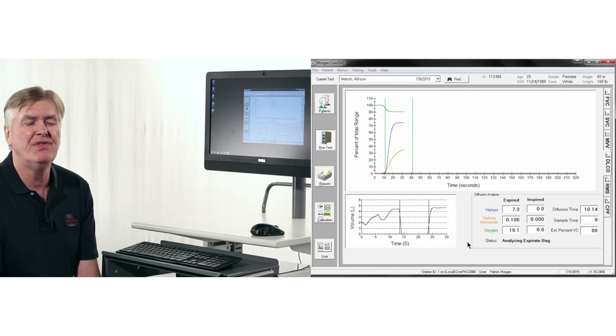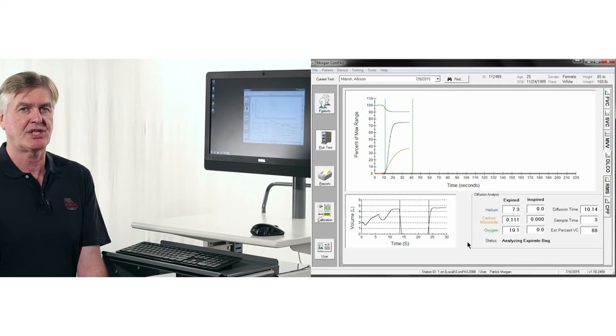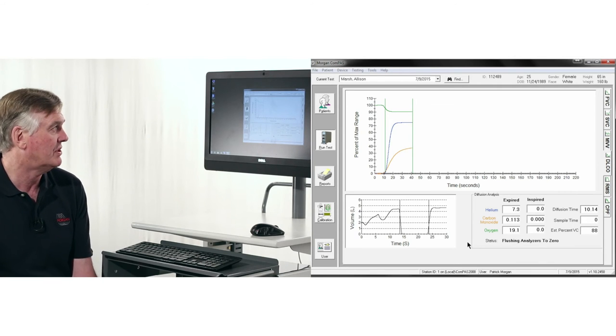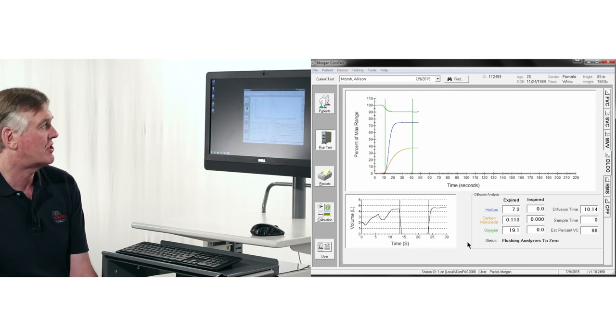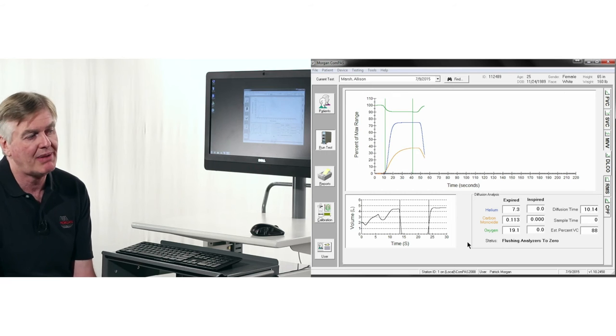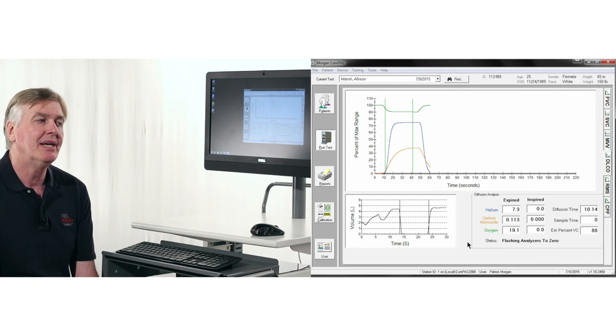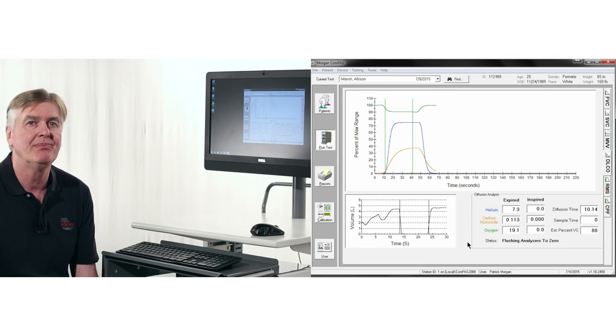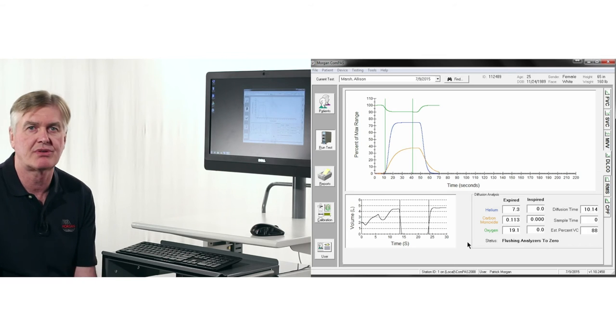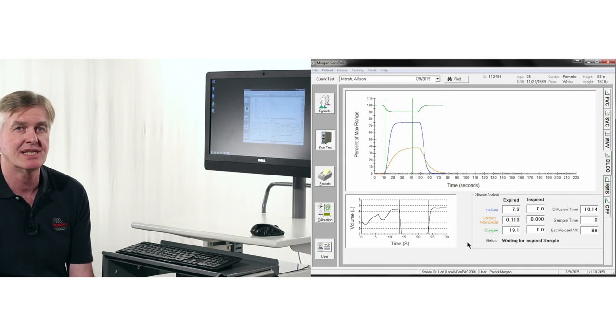So here, it's very unusual on the TransAir 3, if you've managed to get the patient to full inspiration, to ever have to do more than two diffusions. So the screen is showing you that it's now captured the expiratory sample. We return the analyzers to room air conditions, and then we'll measure the bag sample. The reason we do this is not only for the timing, but if you had delayed for a long time between tests, it's possible that some of the helium in the sample has diffused through the plastic. So we make sure we measure both the inspiratory and the expiratory gases exactly.